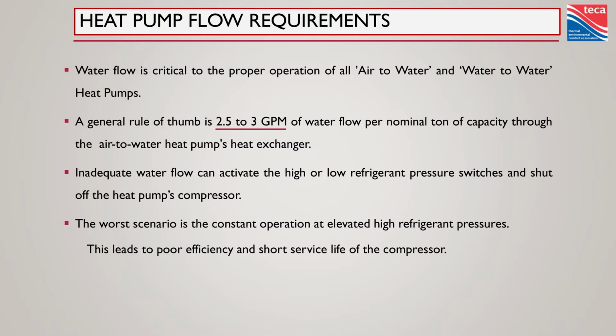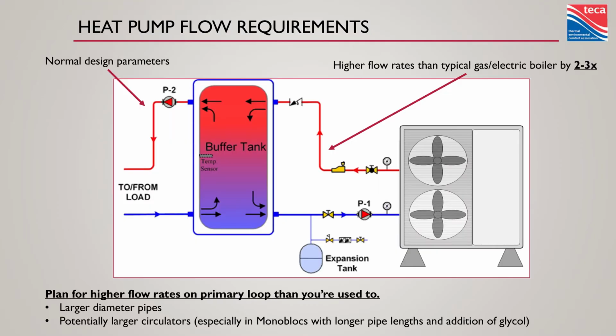Inadequate water flow has a detrimental effect, and of course we can ultimately just destroy the equipment if we run it with too low of water flow for too long. So let's talk buffer tanks again for a minute. This is a 4-port buffer tank. The 4-port buffer tank method is very popular. It's very easy to achieve hydraulic separation.